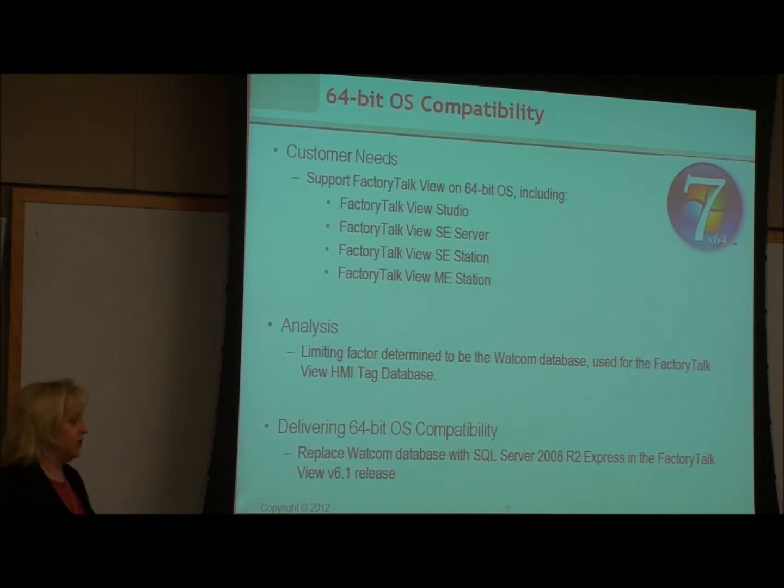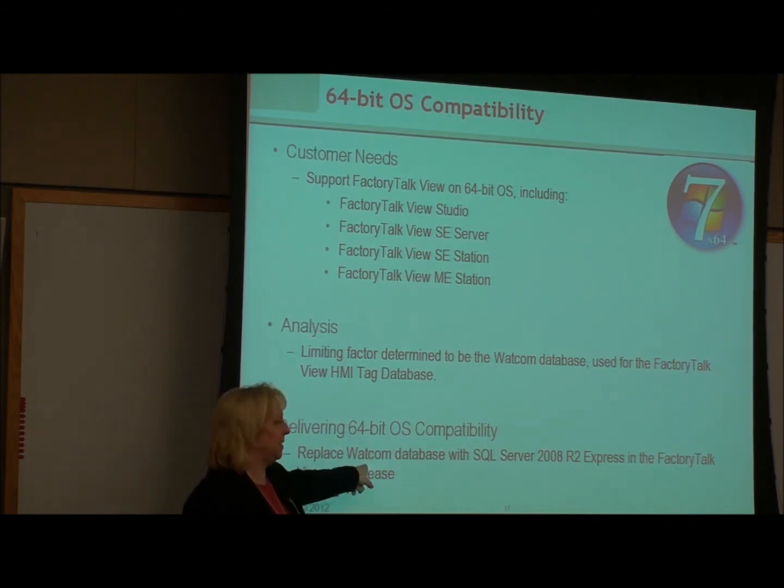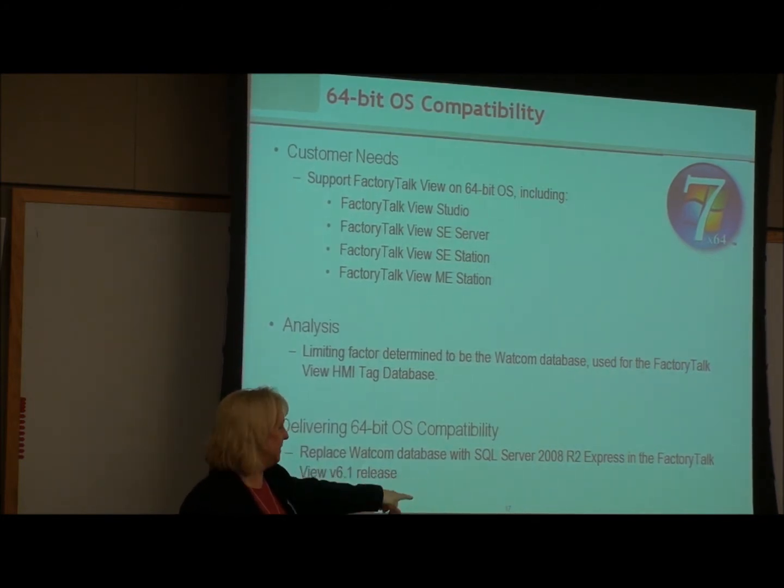Factory Talk View ME version 6.1 was the first version that became available on Windows 7 64-bit — version 6.0 had only 32-bit. RSView Enterprise is the core of Factory Talk View. The reason there are challenges moving to 6.1 is that in the 32-bit world, something called the Watcom database was used underneath. When moving to 6.1 64-bit, this database and the underlying information of your application did not port to 64-bit, so Rockwell changed to SQL. That's under-the-hood, but it creates some important considerations.